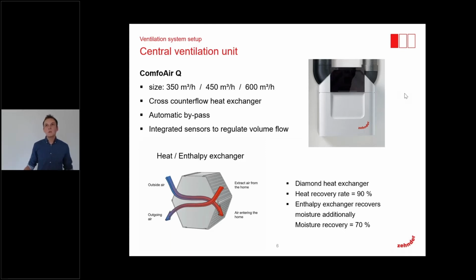It's a diamond heat exchanger, but we also have an enthalpy heat exchanger, which not only recovers the heat but also humidity. So at the end, you have a slightly higher efficiency due to the recovery of sensible energy, which relates to temperature, and we also recover latent energy, which relates to humidity. So in total, we have a little bit higher efficiency. I want to show you a short video now about our enthalpy exchanger, where they explain how it works and what benefits it brings to us. One moment, please.